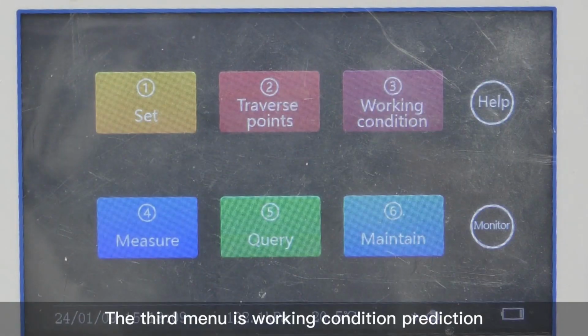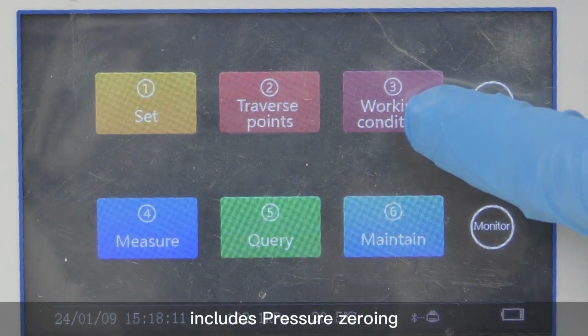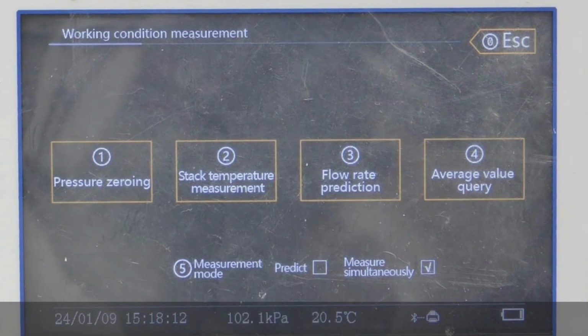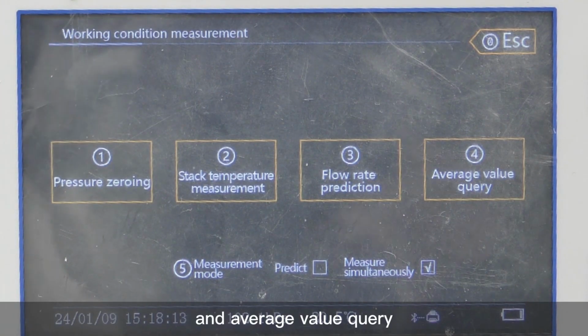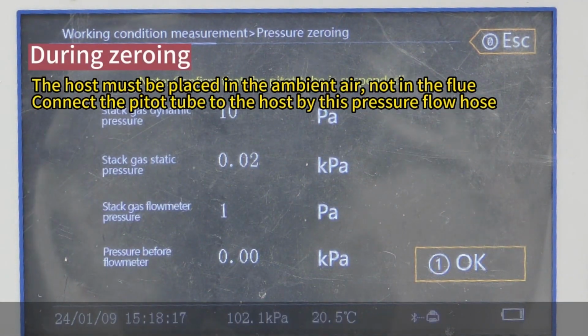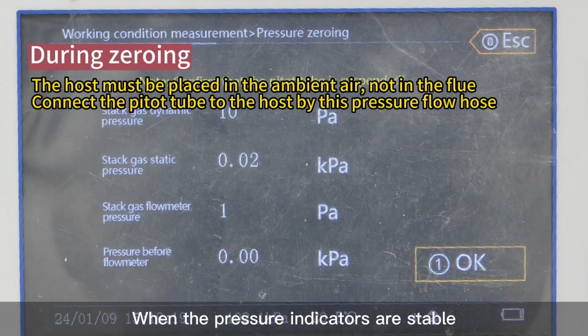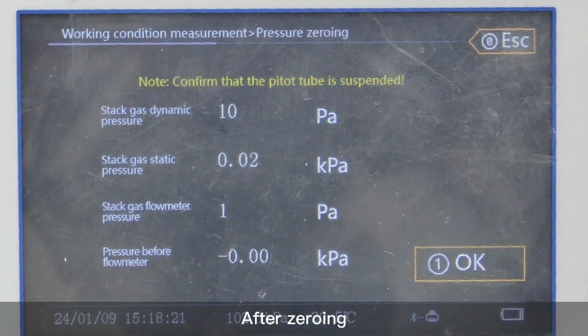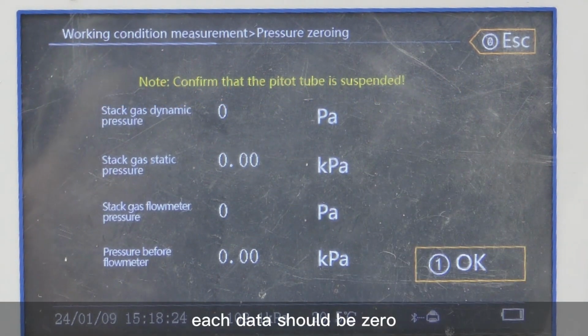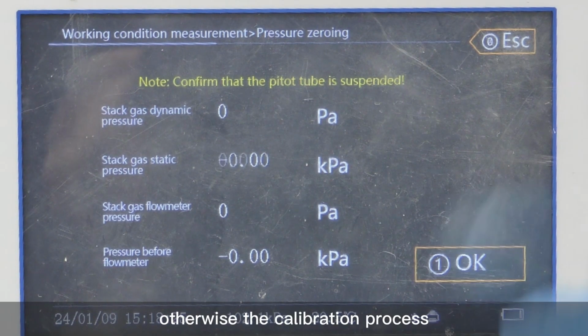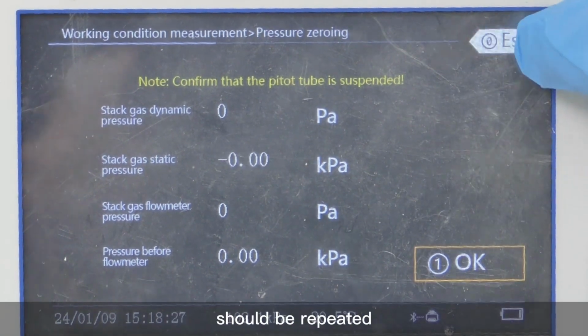The third menu is working condition prediction. Includes pressure zeroing, stack temperature measurement, flow rate prediction, and average value query. Enter into pressure zeroing interface when the pressure indicators are stable. Click OK. After zeroing, each data should be 0. Otherwise the calibration process should be repeated.